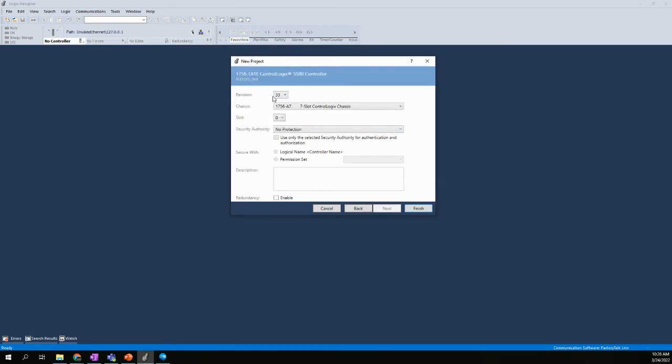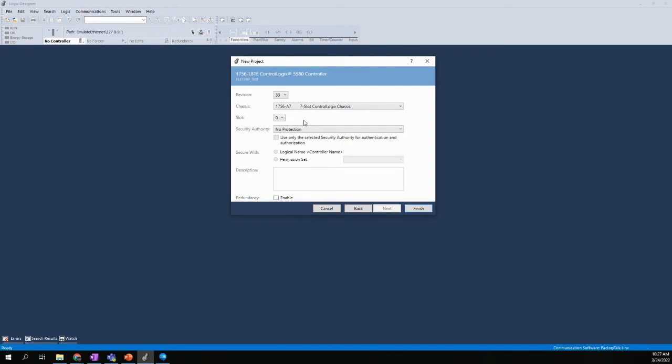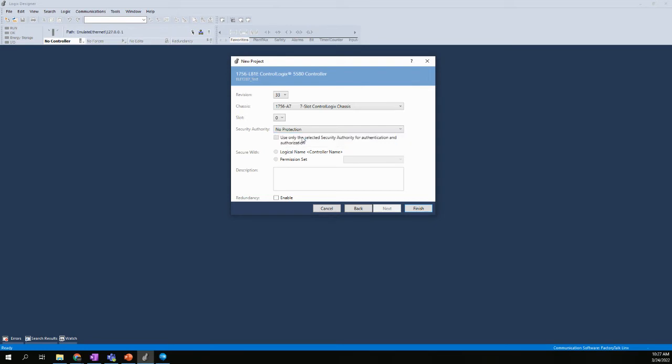The next option here is basically the revision. We want to keep this at version 33. The chassis size, A7 is default, and that's fine. We can keep that as well. You have options for the various chassis sizes that are available. There's four slots, seven, 10, 13, and a 17 slot. So A7 is fine for the seven slot. We'll keep the CPU in slot zero because that matches what we had in the Logix Echo chassis. And no protection is good. You do have options to enable security. I would highly suggest you do not do that. You could potentially lock yourself out from getting into this project afterwards. And we'll say finish.